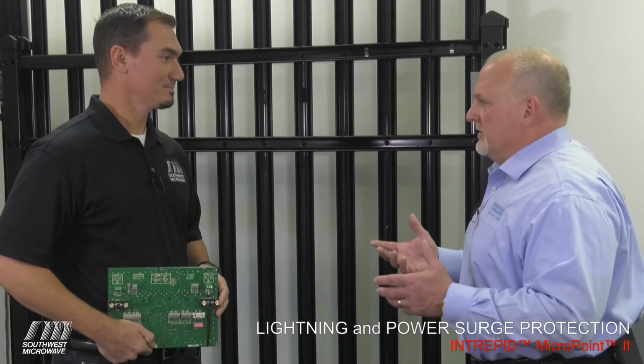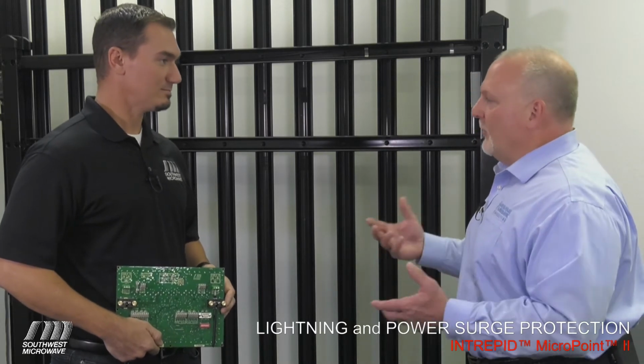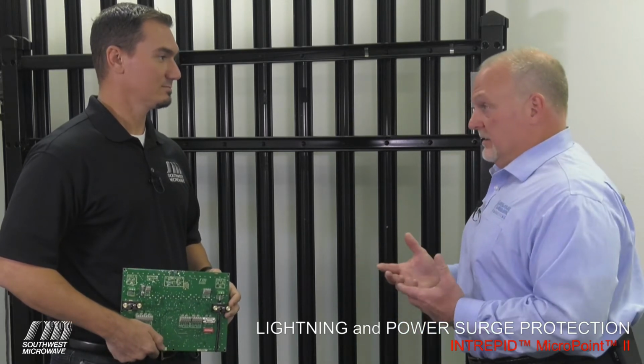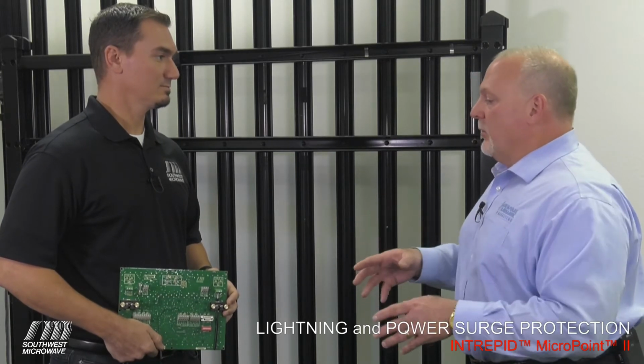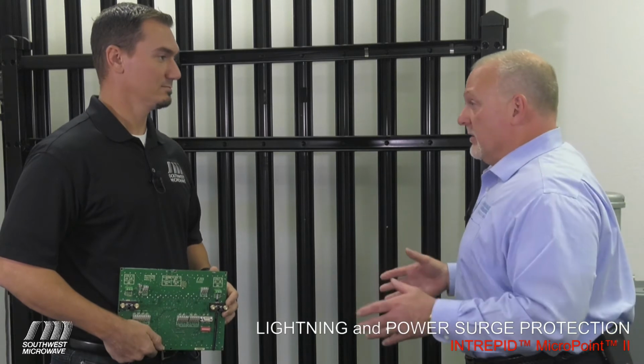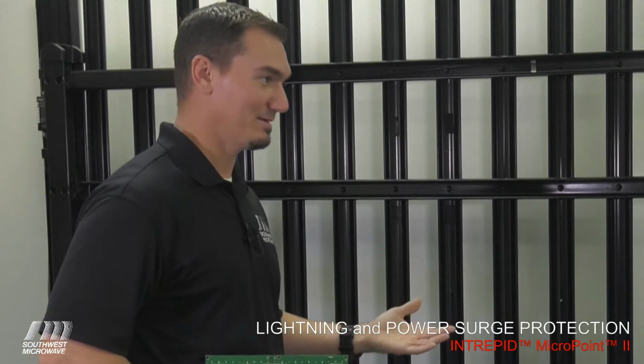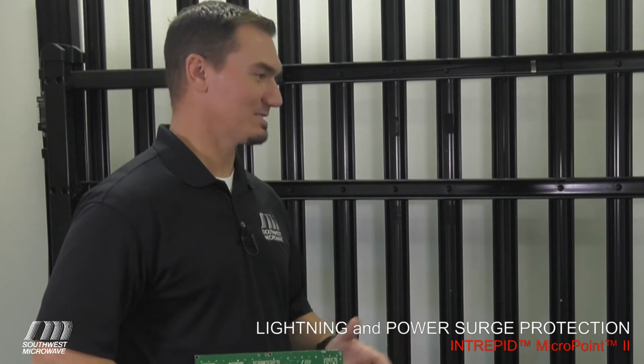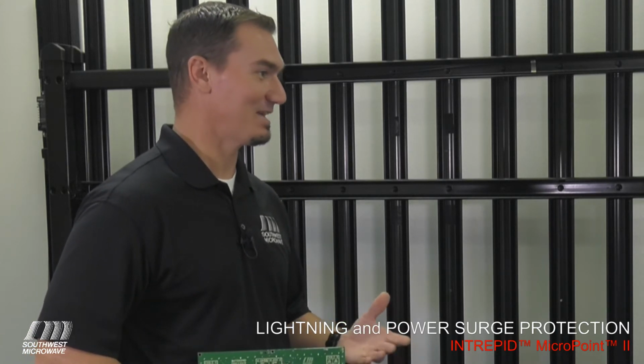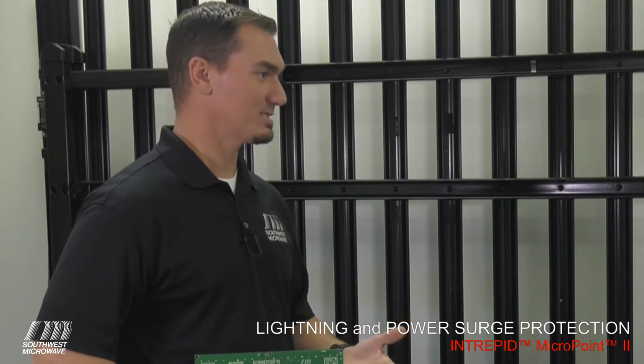And like fiber optic units that are out there, fiber optic systems, yeah, it's a piece of glass and it's immune to EMI, RFI, lightning and that, but even the power is susceptible to lightning and issues of that nature. So again, you're protecting both the AC power, communication, wiring, everything across the board. Sure, and when we're dealing with fence-mounted sensors, there is always an electronic component and there's always a sensor component. So copper-based systems are no more susceptible to electronic or surge protection damage, lightning damage than the fiber optic systems are. It just depends on where the electronics are and what protections are in place to protect those circuits.